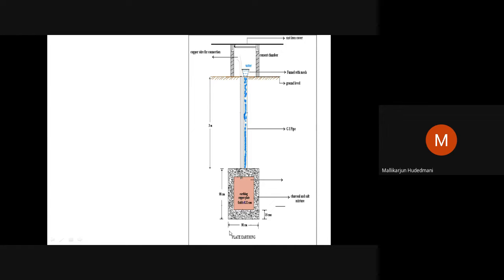area becomes conducting. This way, it has the ability to dissipate higher fault current, in the range of hundreds to 1000 amperes, because the material you have used, a copper plate or aluminum plate, is a very good conductor. That good conductor is buried deep into the earth crust, a minimum of 3 meters below the surface. Then its contact is brought to the meter box wiring side, where one neutral, one line and one ground will run all around the premises. Whenever any electrical device develops a fault, the earth pin drives that current into the earth pit. This is how the safety precaution is built into the earthing.